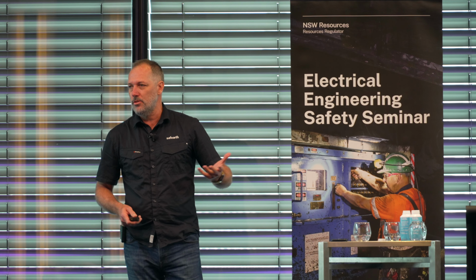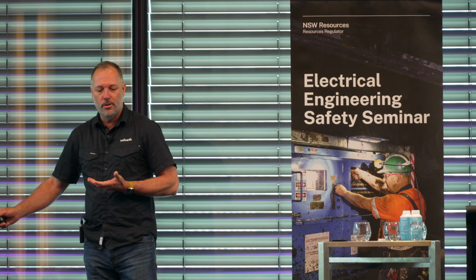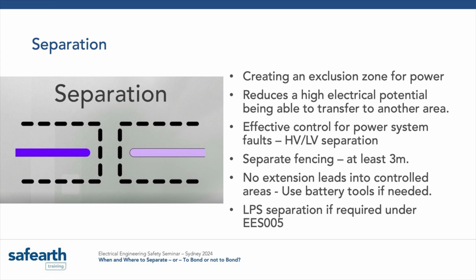Separation, on the other hand, is where you intentionally try and make things stay at different potentials. During an earth fault, maybe one system will rise to a potential and you want the other thing to absolutely not. A very good example of separation is in HV/LV transformers. We use them in the mining environment, but also in the distribution environment around more country areas, where you intentionally separate the high voltage earthing system from the low voltage earthing system. You're trying to keep the voltage on the low voltage system as low as it can be more often.